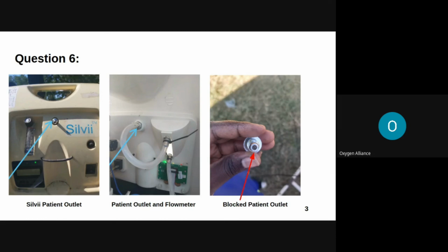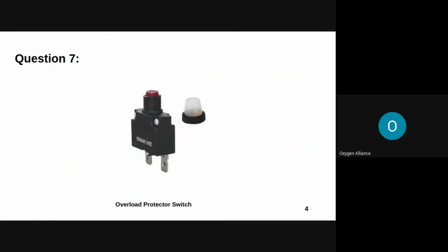Another step to take is to set your multimeter into continuity mode, and then you conduct a test on the power cable and the compressor wires. Replace a part or fix any fault if you find them. In some cases, a compressor might have an internal fault, like overcurrent draw or insufficient torque, which causes the overload protector switch to trip. To see if this might be the cause, disconnect the compressor from the motherboard and switch on the machine. If it does not trip, then you need to replace the compressor. Thank you, Maui. Thank you very much, Mteto, for that explanation. I hope that was clear for everyone.